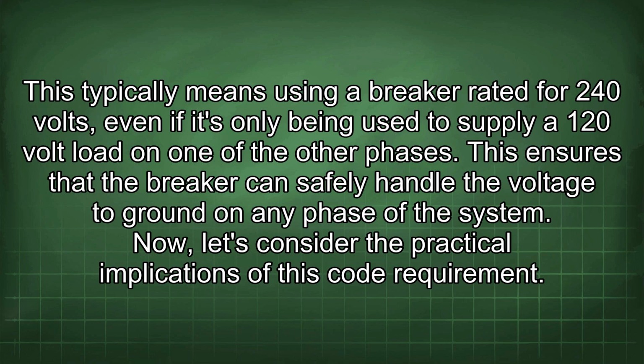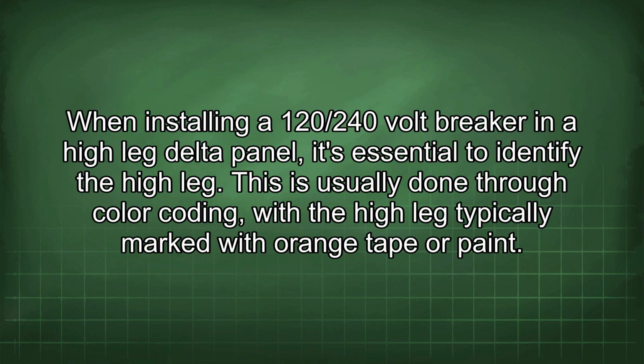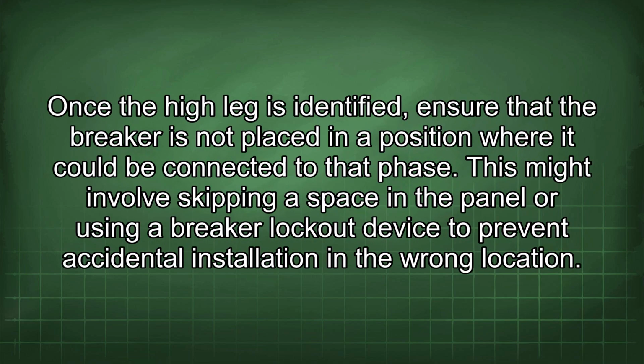Now let's consider the practical implications of this code requirement. When installing a 120/240 volt breaker in a high-leg delta panel, it's essential to identify the high leg. This is usually done through color coding, with the high leg typically marked with orange tape or paint. Once the high leg is identified, ensure that the breaker is not placed in a position where it could be connected to that phase. This might involve skipping a space in the panel or using a breaker lockout device to prevent accidental installation in the wrong location.